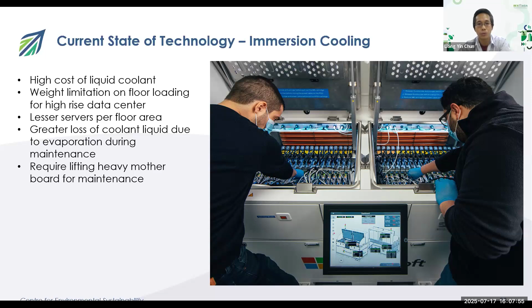For the two-phase liquid, if you open the tank like this, it will start evaporating. But even if you are using an oil base, you have to clean the oil during maintenance. Imagine doing maintenance in this case: you need a crane to hoist up the motherboard and wait for the oil to drip before you can do any maintenance. That's the issue with using this kind of immersion cooling.